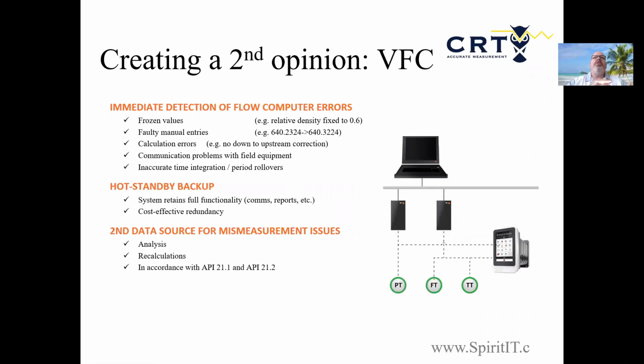The other thing we're able to do with flow computers is also create virtual flow computers on top of flow computers. We're able to take a flow computer that's out there and run a software flow computer over top of it, and check for mismeasurement issues on the primary flow computer, or groups of primary flow computers. So it's a backup system.